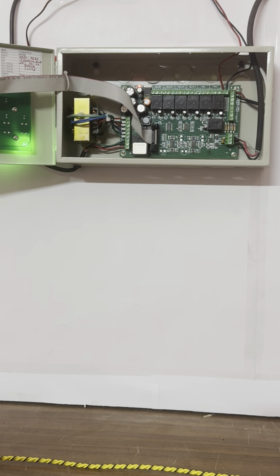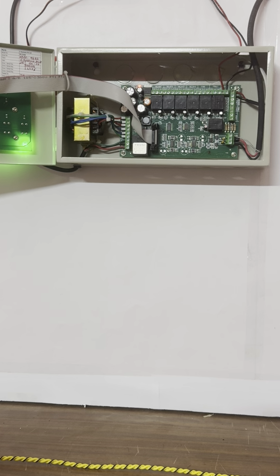Apart from the hardware integration, there is a soft point integration provided in the panel. This is a default feature which comes with all water leak detection systems manufactured by Systems Pvt Ltd. It is an inbuilt feature called the Modbus RTU RS485 port. All these zone statuses can be monitored through this RS485 port. The only recommendation is that you use a 2-core 1.5 square mm shielded braided copper cable, which has to be terminated to the DDC controller or a dedicated BMS software which monitors the status of the water leak detection panel.